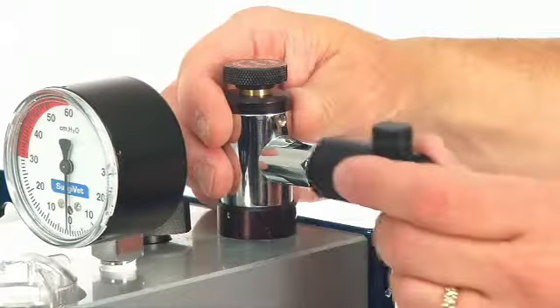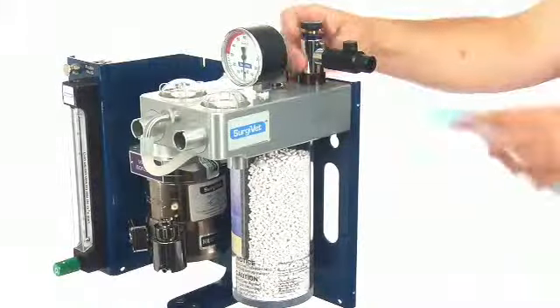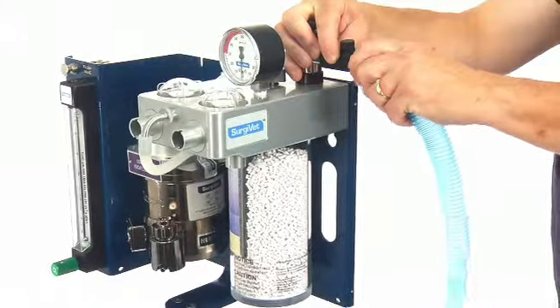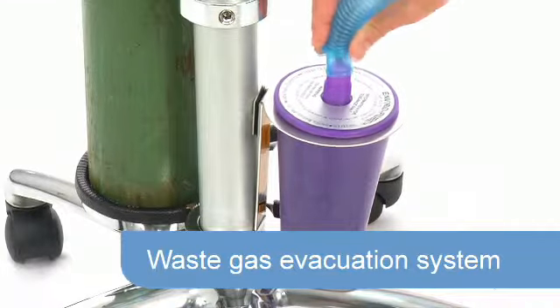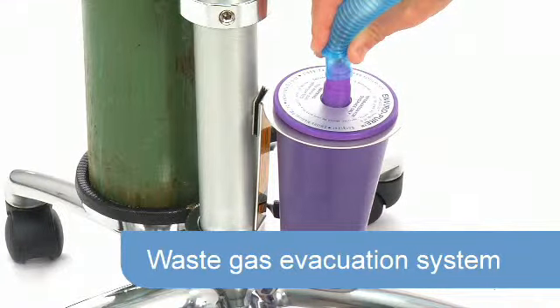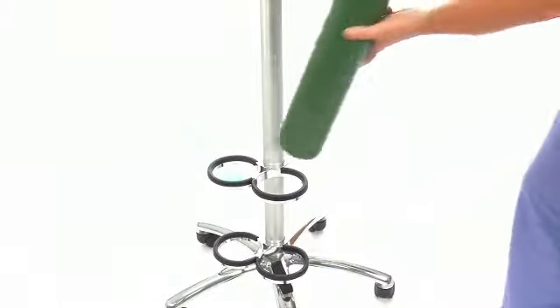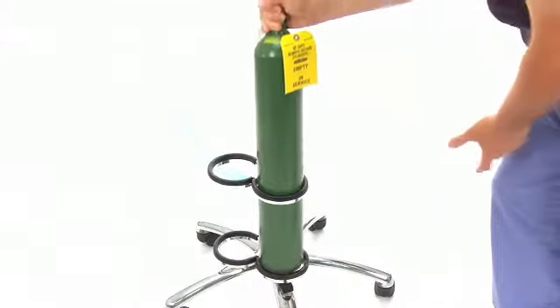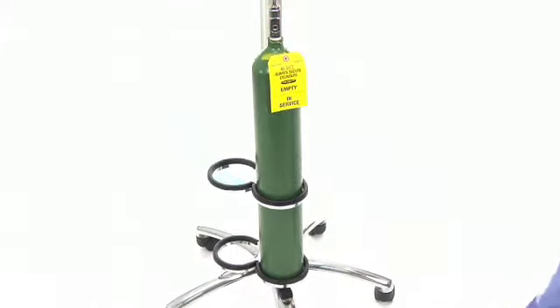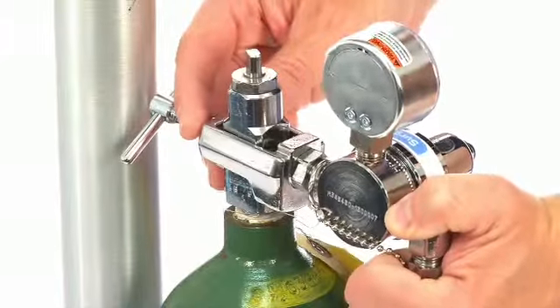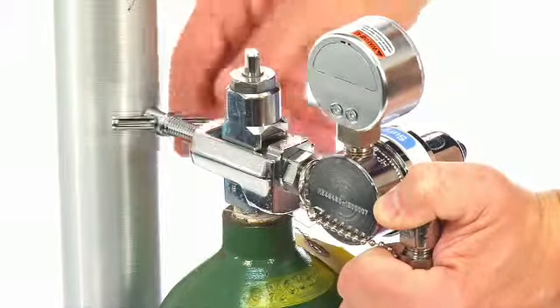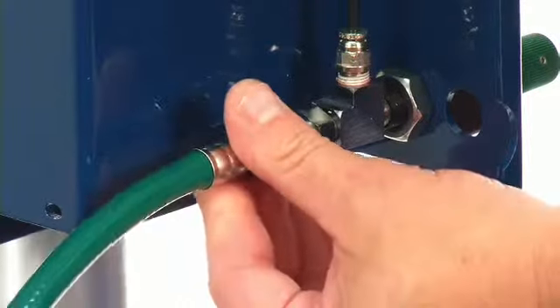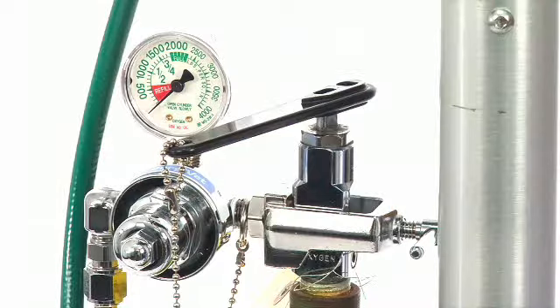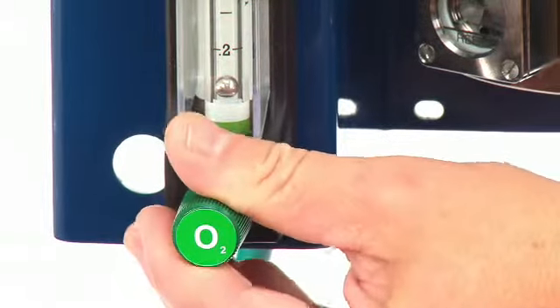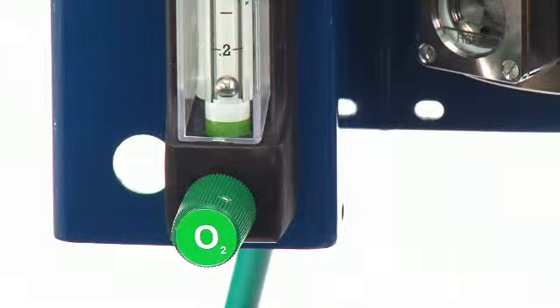Secure the pop-off occlusion valve onto the pop-off valve. Attach the 19mm waste gas scavenging tubing and connect it to the waste gas evacuation system. The CDS 9000 machine is designed to work with a variety of delivery gases. The delivery gas is connected to the flow meter on the back of the machine using the appropriate DISS connection. The delivery gas source and the flow meter should both be in the off position during this connection.